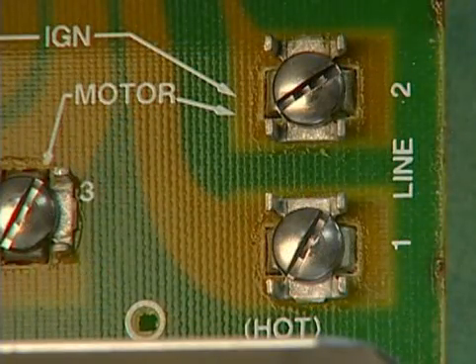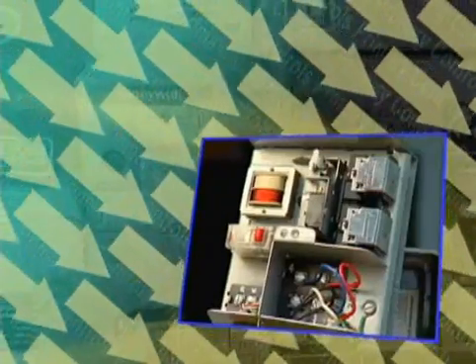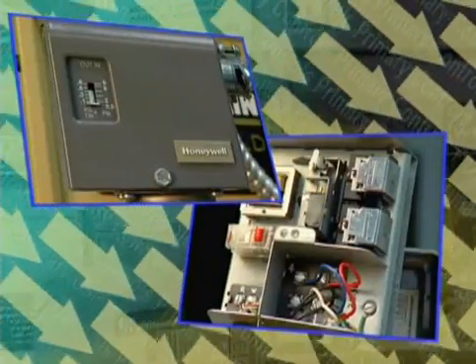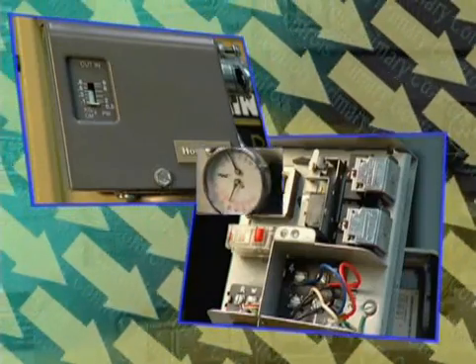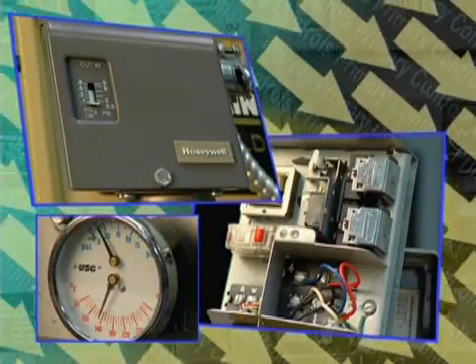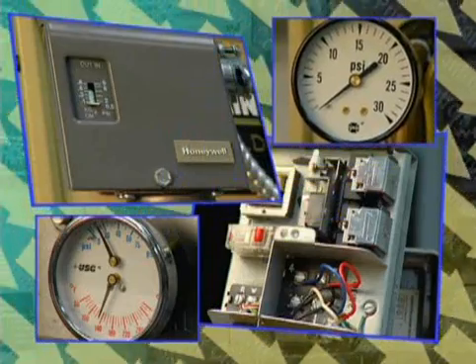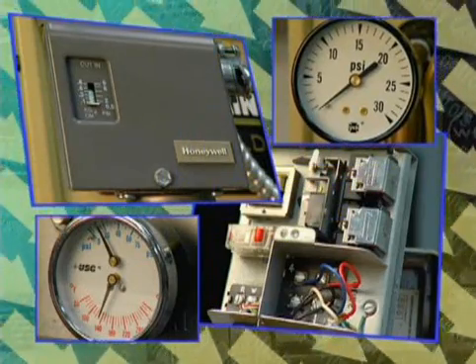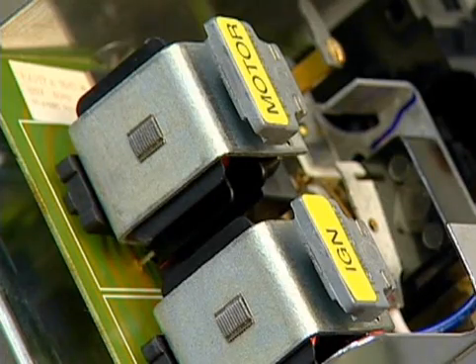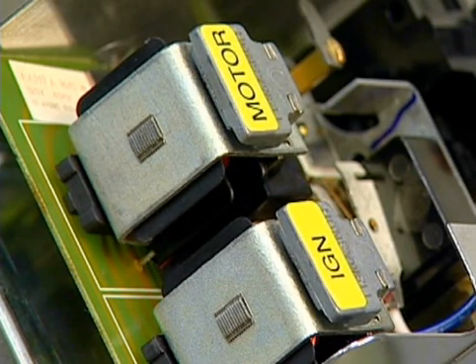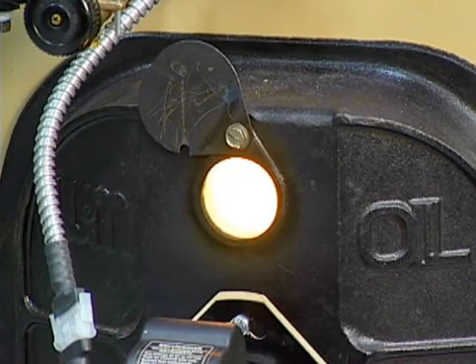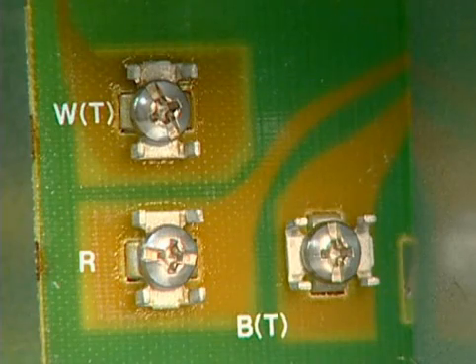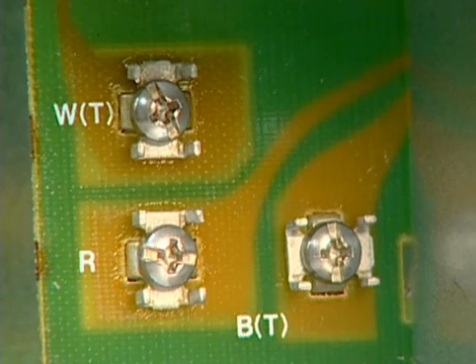All primary controls have 120-volt AC line voltage circuits. In a heating system, line voltage is supplied to the primary control through the limit control when the temperature in a water heater, boiler, or furnace, or the pressure in a steam boiler is below the limit setting. Once the limit control is satisfied, it breaks or opens the circuit, de-energizing the primary control and shutting down the burner. Most primary controls also have 24-volt AC low-voltage circuits to accommodate thermostats and/or other devices.